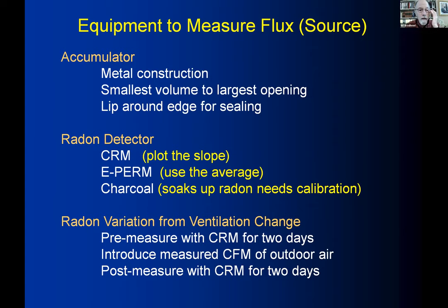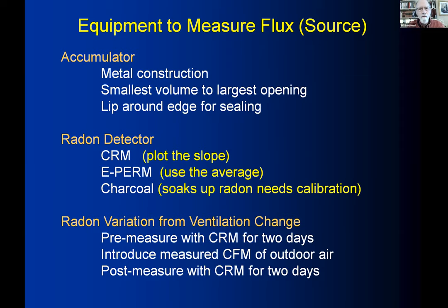The key measurement approach was a ventilation variation test: pre-measure radon for two days, then introduce a precisely measured amount of outdoor air, and measure the radon change. This tells you how much radon is coming from the concrete, what the initial ventilation rate is, and — most importantly — how much additional air is needed to reduce radon levels to acceptable levels.